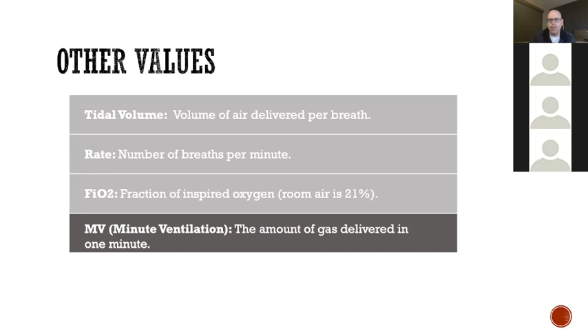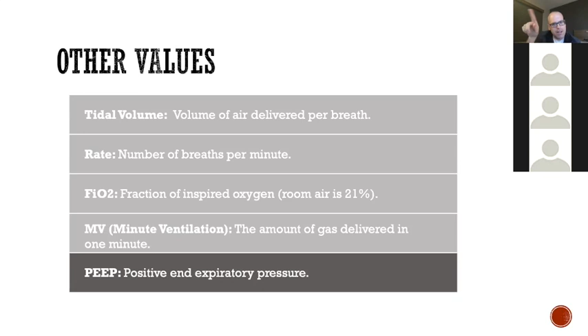Next is PEEP, our positive end expiratory pressure. We'll talk about PEEP in just a second. Another value that I talked about a second ago is rate, but one thing to always look at on the ventilator is how many times they actually breathed in the last minute. When you look at the screen, it'll tell you that. It'll usually be a fancy looking small f. That's their breath rate for the minute. And if your breath rate says that they breathe 32 times, but you have the ventilator set at 12, then you know this patient is significantly over-breathing that ventilator and taking extra breaths.